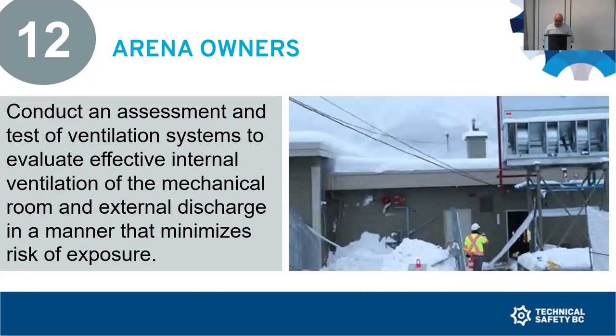This recommendation is that we recommend that arena owners conduct an assessment and test of ventilation systems in all their arenas. So this test needs to evaluate the ventilation and the external discharge from the mechanical room. And it really needs to demonstrate that the system is minimizing the risk of exposure, both for staff and the public. And arena owners will be requesting this test. We're recommending that they do so. And as contractors, mechanics, you'll likely be required to perform these tests of the ventilation systems. We recommend that this test be done on a regular basis. Could be quarterly, could be annually.